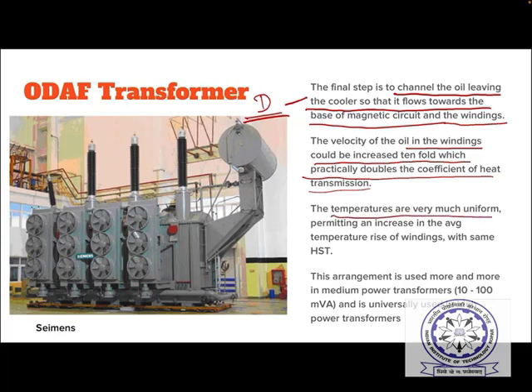Now the temperatures are very much uniform along the vertical position. Therefore, average temperature can be increased now with the same hot spot temperature. See, basically hot spot temperature is the concern where the maximum aging could take place. Therefore, now if winding temperatures are uniform, means everywhere more or less the temperature is same, so we can go close to the hot spot temperature. All other layers of the winding also can go close to the hot spot temperature. Means average temperature will increase. If average temperature increases, what? Average power dissipation can increase. Means what? The power transmission capability increases.